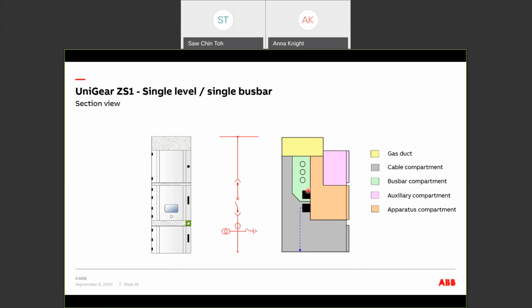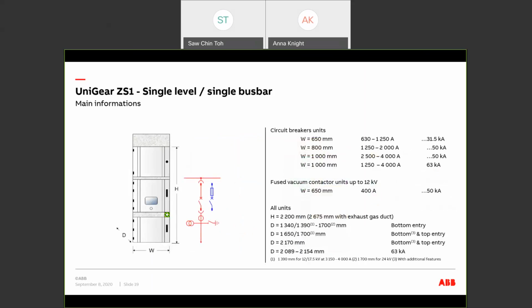And we also have the bus bar compartment running across the top of the switchboard and joining all the panels together. And we have the arc duct at the top of the switchboard. Depending on the rated current, the panel width will range from 650 millimeters to 800 millimeters or 1 meter. Other than the circuit breakers, we can also fit the vacuum contactor in the same 650 millimeter wide panel. The panel has designs available to suit different types of power cable entry, either from the top or the bottom, by changing the panel depth.